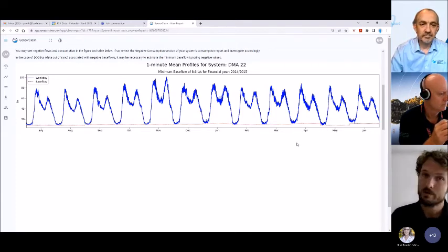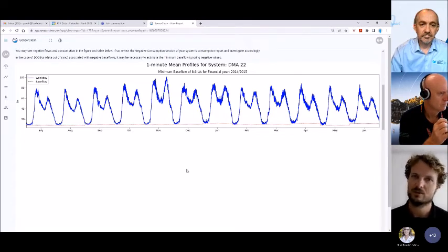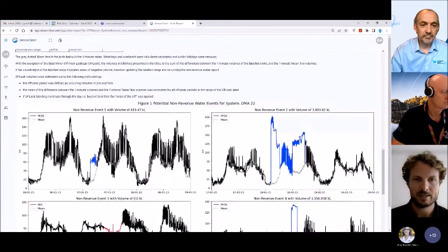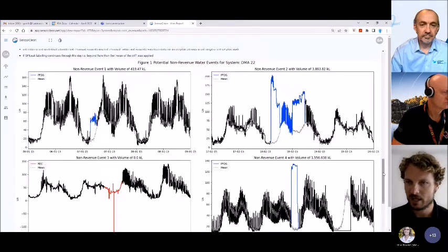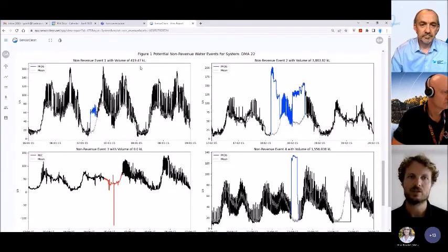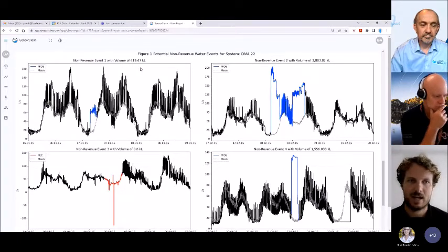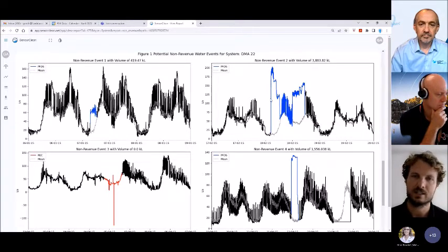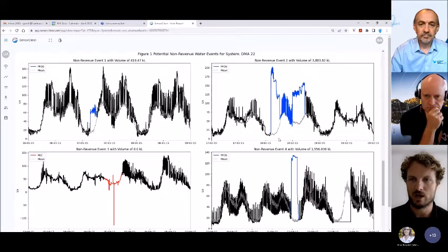So this is only for one financial year. If you've got more, they're going to show up below here, and it's quite useful for comparisons for that minimum night flow as well. So just moving on down to some of the events that we labelled. And in the title of these plots, we've just got the water loss from those events. The grey dotted line that you can see, 1 minute monthly mean, separated for weekdays and weekends. So the water loss is essentially the difference between this blue line and the 1 minute monthly mean there.